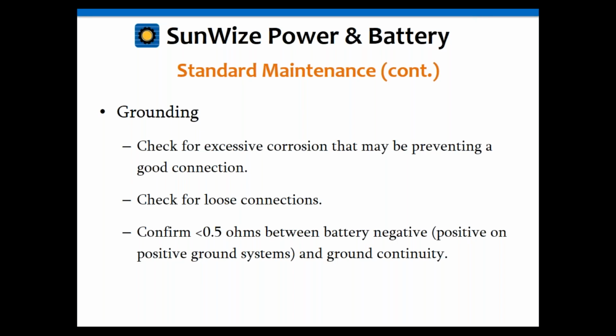And you also want to confirm that you have low resistance, less than 0.5 ohms. This is where your multimeter can come in handy as well. You can set it to resistive measurements, and then you can check that, make certain it's less than 0.5 ohms. Now, that's not with respect to earth ground. That's just between the grounding system. So somewhere between your battery negative terminal, or positive on a positive ground system, and your ground rod or your ground system, you want to confirm that it's less than that.